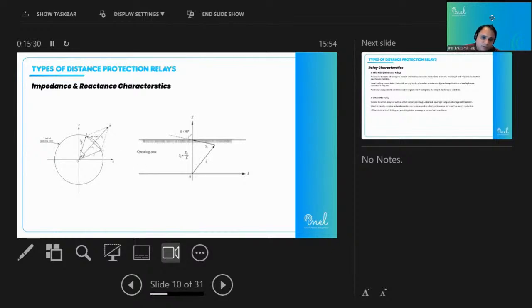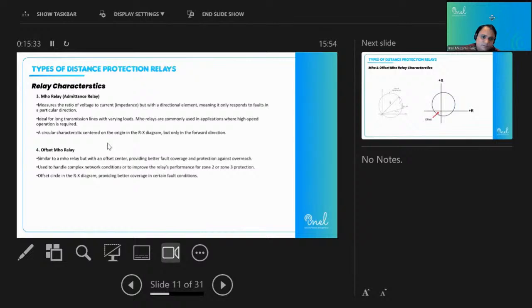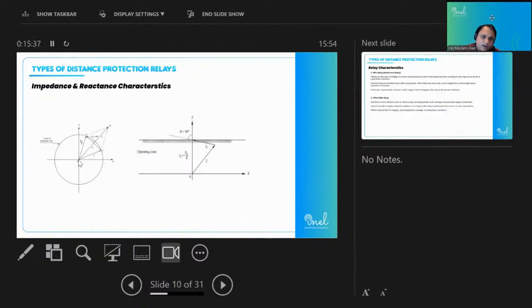If there is a very small length of line, then the circle will become very small. And if the R value increases beyond this point, say at this location there is an R, then this fault will not be detected by this circle, because what we have learned previously is that if our impedance is greater than this circle, then this relay will not operate. But if the impedance falls inside this circle, then this relay will operate. And if there is a fault at this location, but due to resistance the characteristic moves from this location to this location, then this will not be detected by the transmission relay.